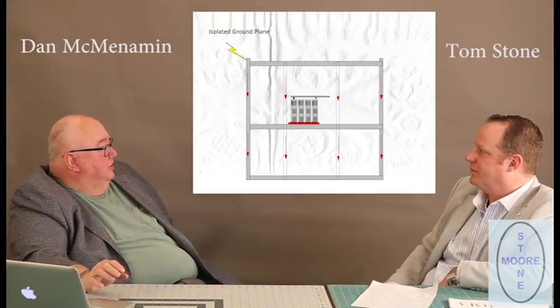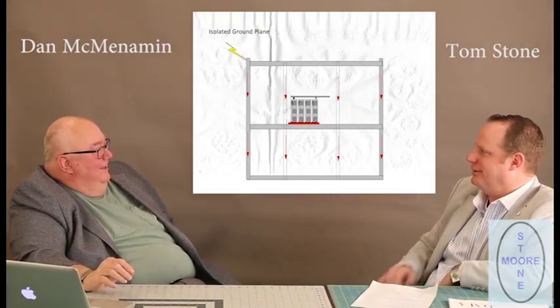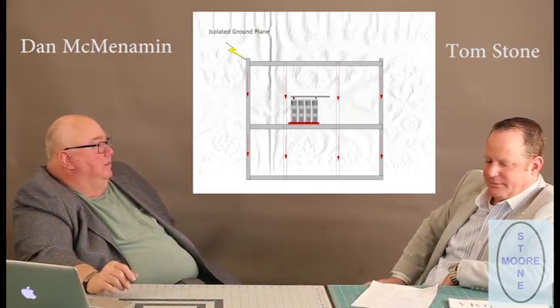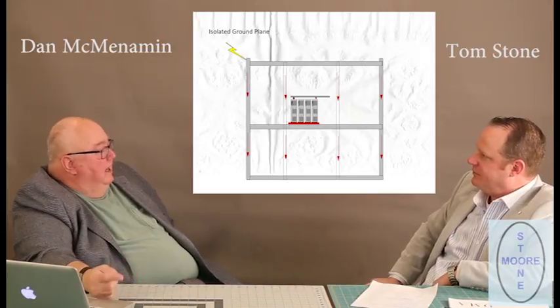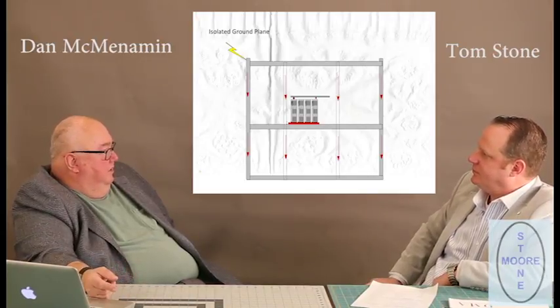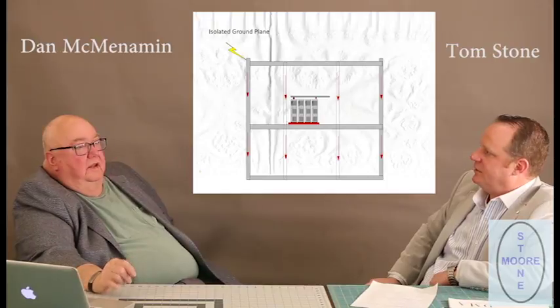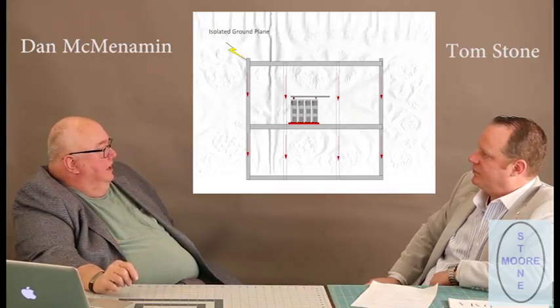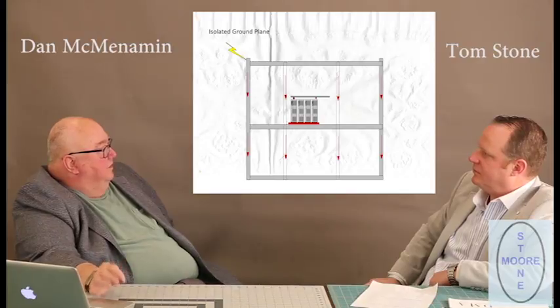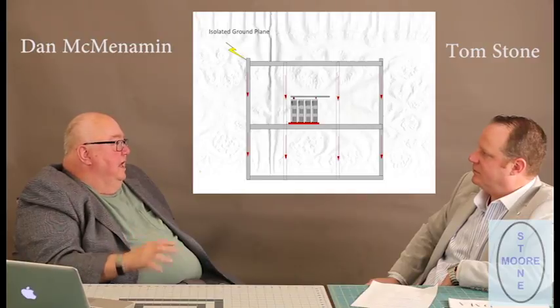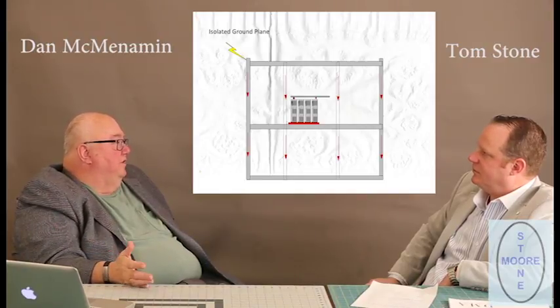And really, it's kind of an electropolitical issue. I'm probably telling tales out of school here, but this is your school. You can say whatever you want. In the early days of the RBOCs, they had this problem in the analog switching systems. By the time they got around to digital switching systems, our standards guys at the time, Bellcore, had only one standard for grounding, and it was grounding for electronic switching systems. So along came digital switching, which was an electronic switching system. The rules were already written, and they required isolated grounding.